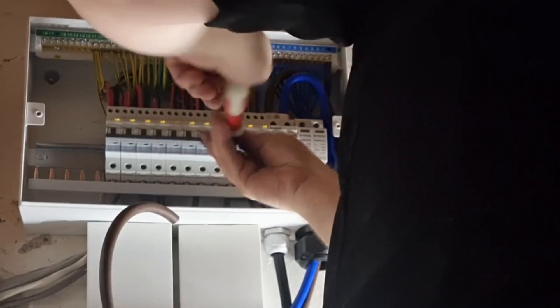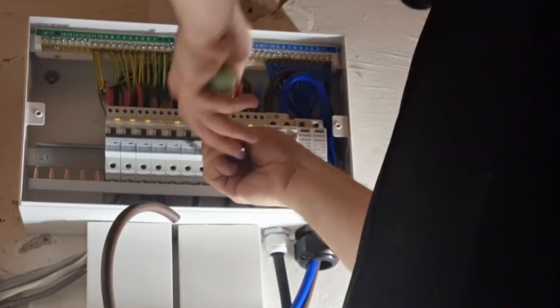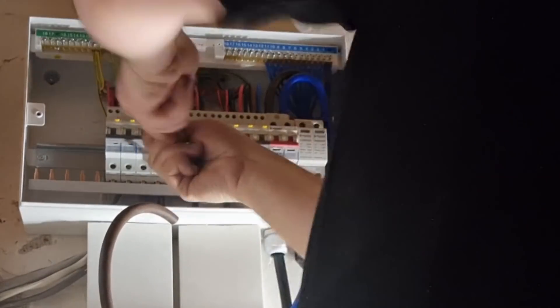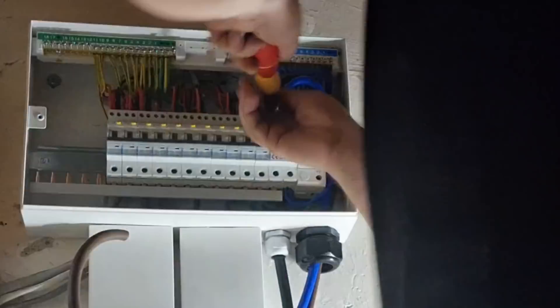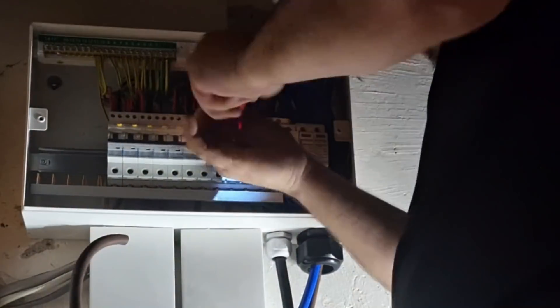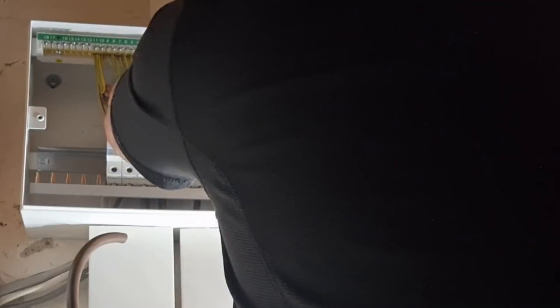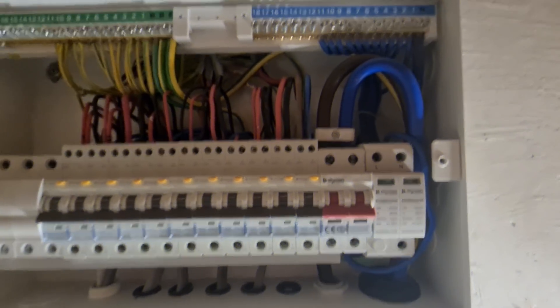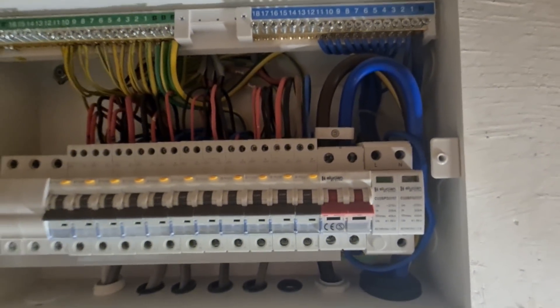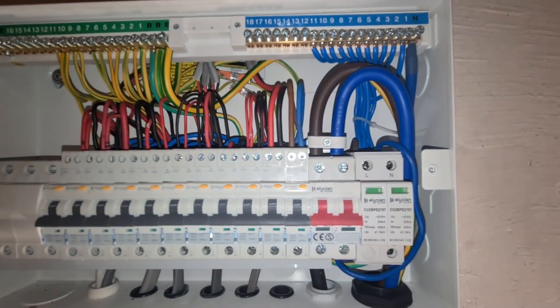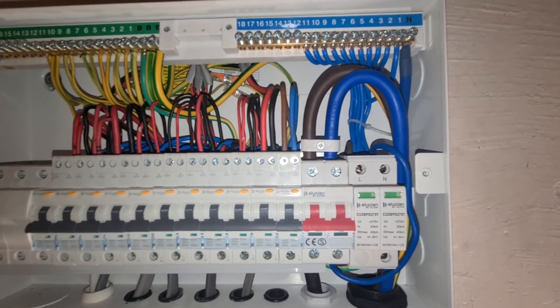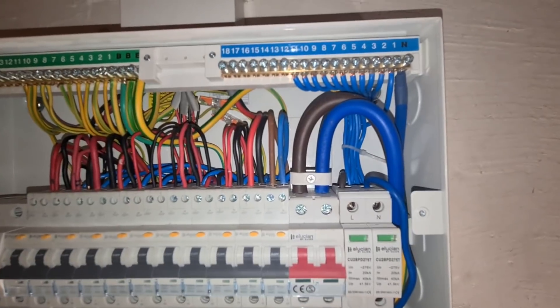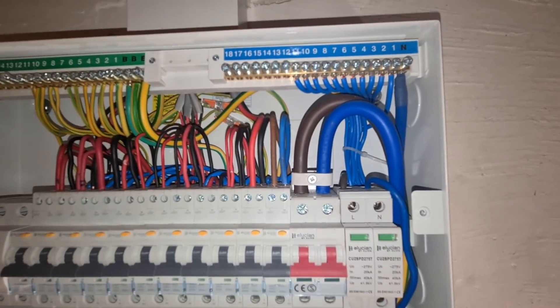So they came and made the isolation from the old boards pre the works and then we get them back later on to come and energize. We don't faff around with any of that. See they're just checking the busbar, and at this point I haven't realized that I need to strip out a couple of the mounting posts off the busbar because of the SPD. So this comes as a 16-way board and by the time you've fitted the SPD obviously that drops it down to 14-way. So you just need to take a couple of those off and I forget every time.